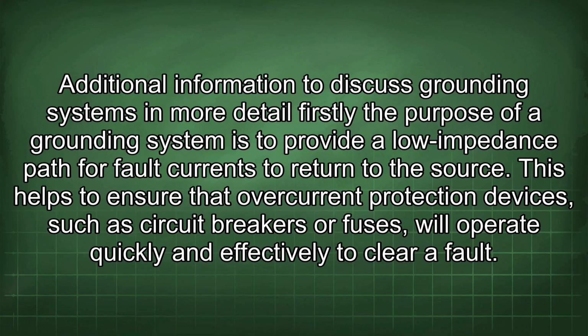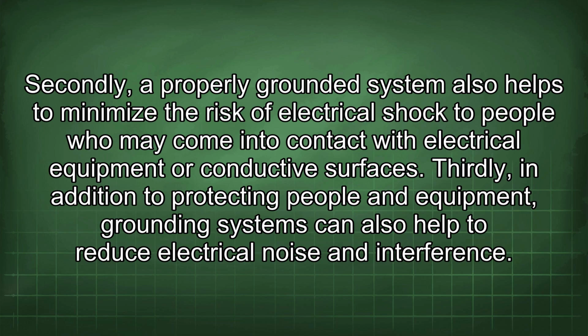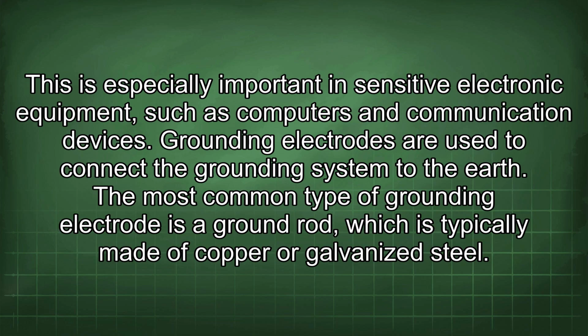Firstly, the purpose of a grounding system is to provide a low impedance path for fault currents to return to the source. This helps to ensure that overcurrent protection devices, such as circuit breakers or fuses, will operate quickly and effectively to clear a fault. Secondly, a properly grounded system also helps to minimize the risk of electrical shock to people who may come into contact with electrical equipment or conductive surfaces. Thirdly, in addition to protecting people and equipment, grounding systems can also help to reduce electrical noise and interference. This is especially important in sensitive electronic equipment, such as computers and communication devices.